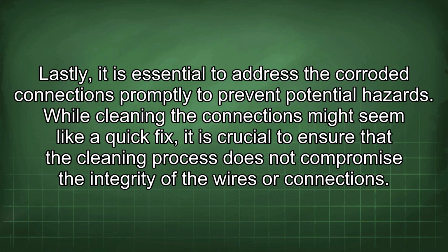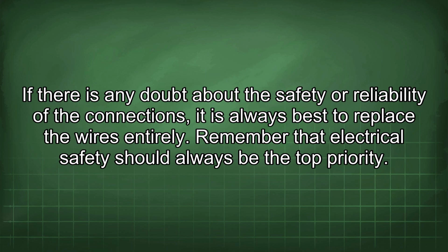Lastly, it is essential to address the corroded connections promptly to prevent potential hazards. While cleaning the connections might seem like a quick fix, it is crucial to ensure that the cleaning process does not compromise the integrity of the wires or connections. If there is any doubt about the safety or reliability of the connections, it is always best to replace the wires entirely. Remember that electrical safety should always be the top priority.